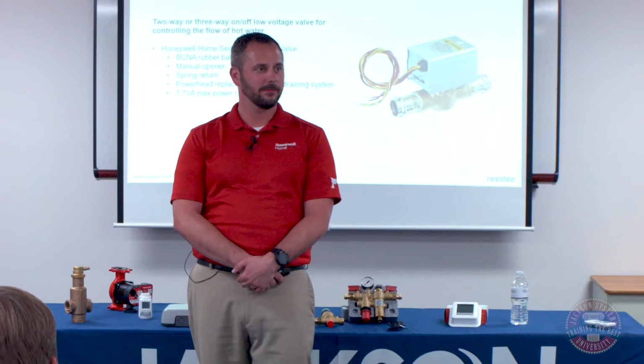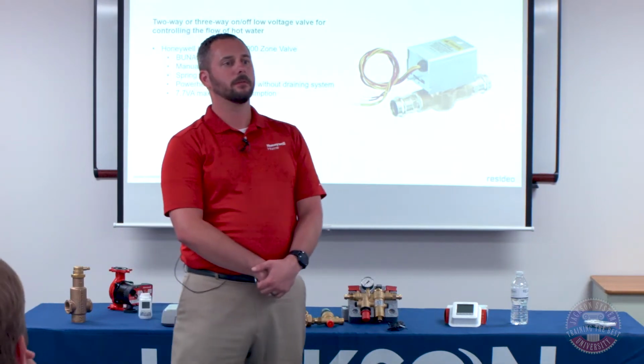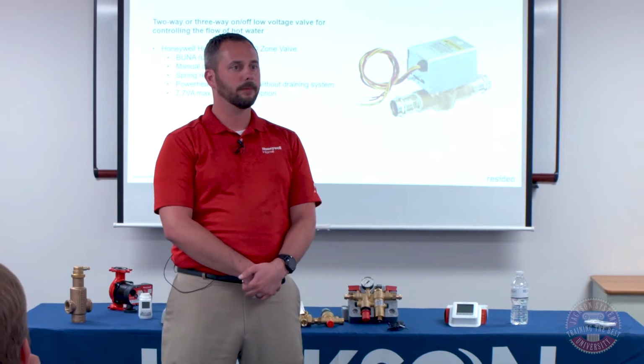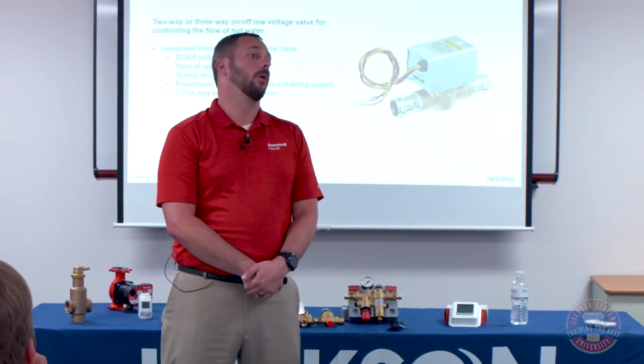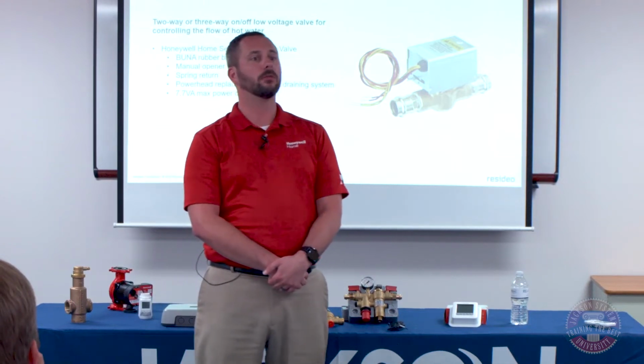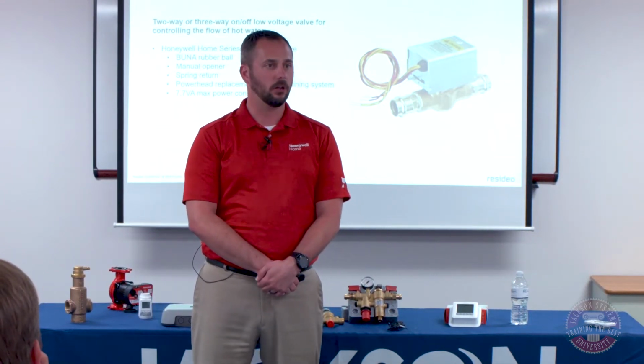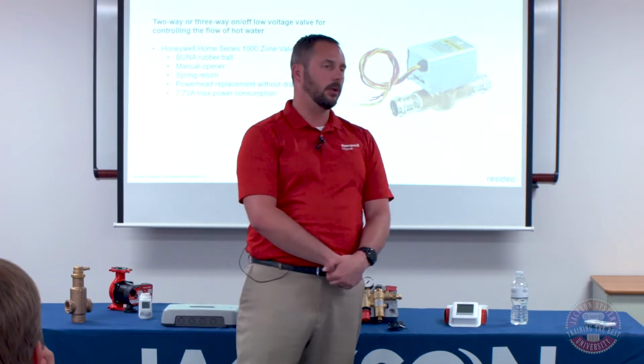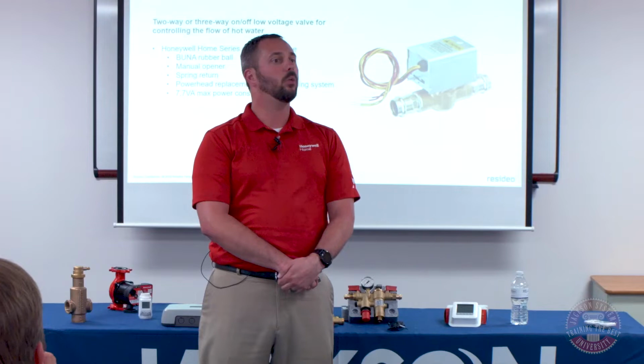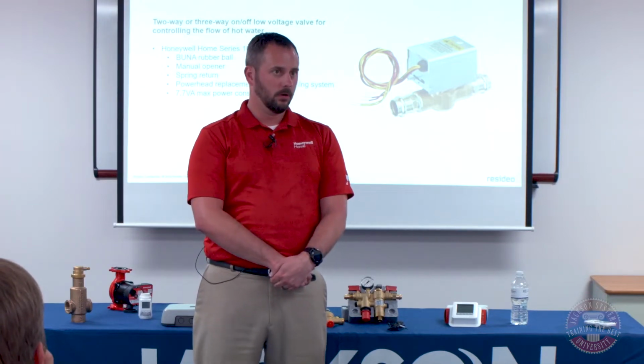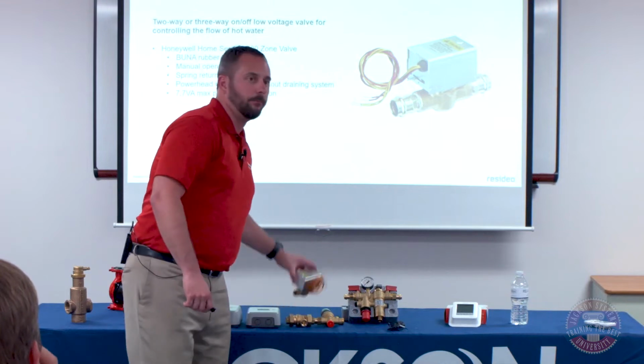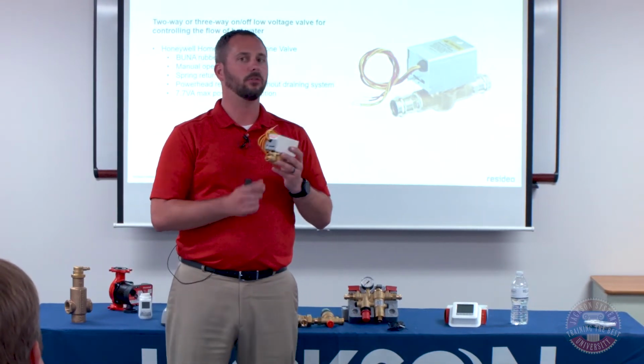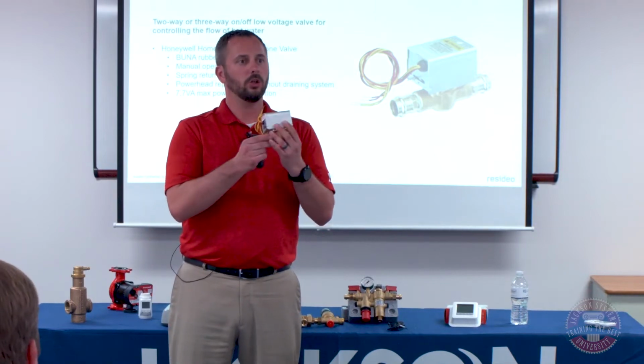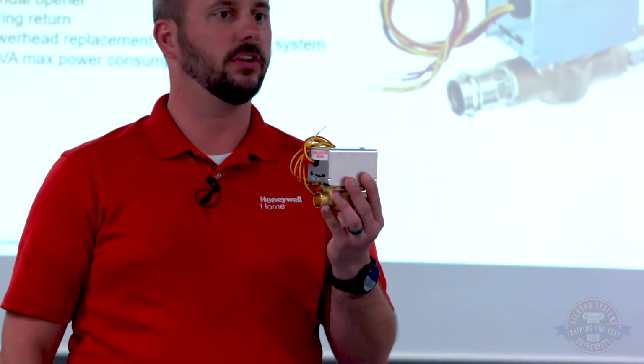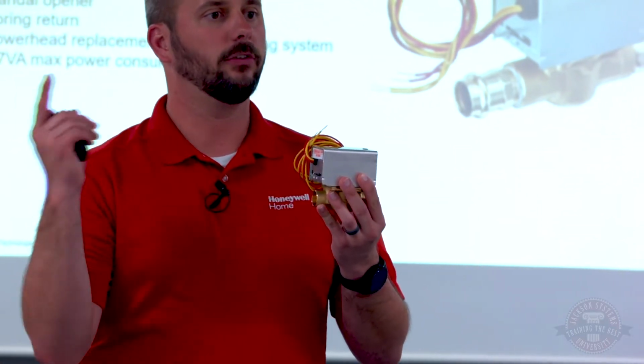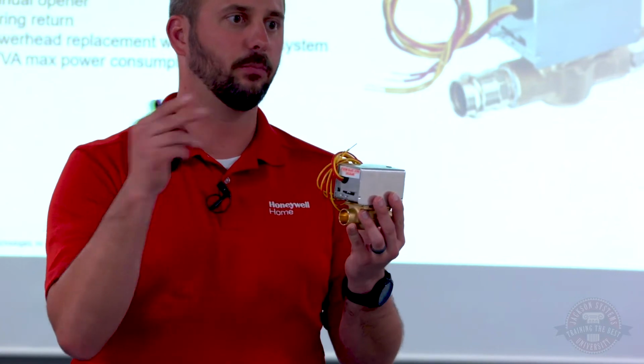Ricardo asked, is the low voltage power to the zone valve constantly energized? No. These are spring return valves, so if it does not have power, that valve will be closed. Or actually, I think I know what he may be asking. When you go to activate our valve, it will need 24 volts consistently. With this series of zone valve, which is by far the most common in heating systems, you have to give it 24 volts and maintain 24 volts to keep it open. When you kill the power to it, it's basically going to close, because that spring is going to draw it back.